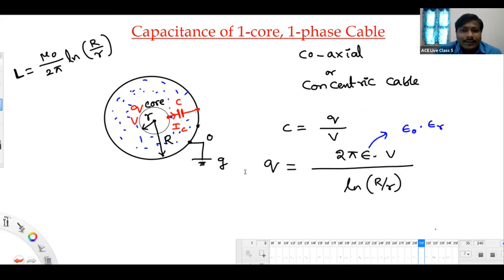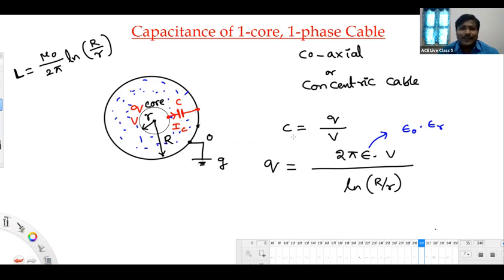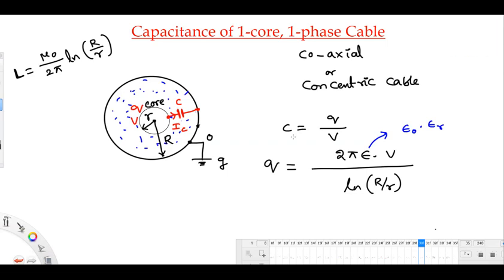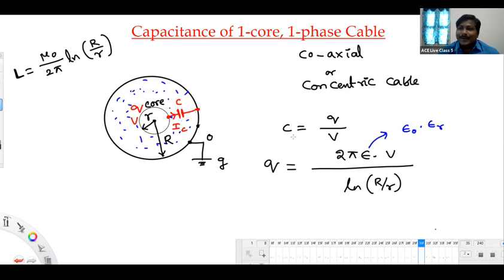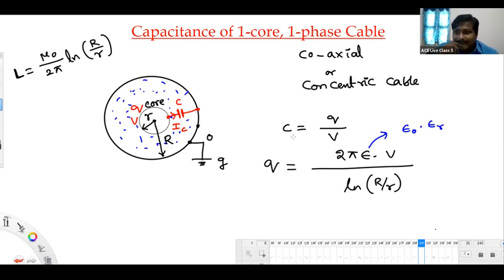Yeah, tell me, Sai, Naveen Sai, tell me. Sir, we are using spark gap for protection of series capacitor, no, sir? Yes, correct. In the faulted case, when the spark gap is short circuited, capacitor voltage is also zero, that's it, sir. But again, whenever the spark gap got broken, sir, it will continue to carry the current, right? Yes, sir. That current flow, that arc will be sustained.